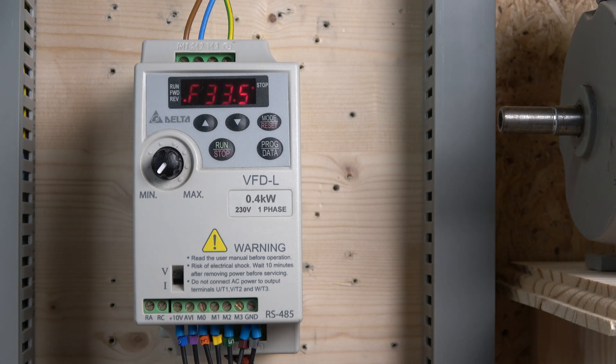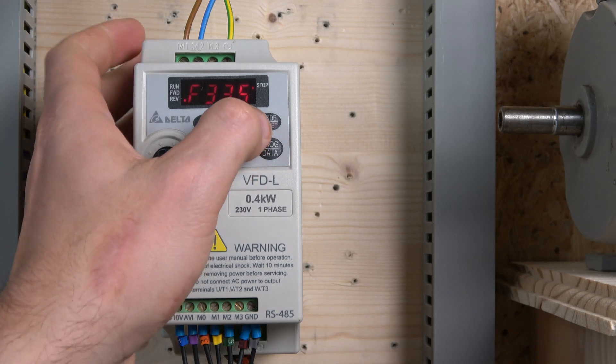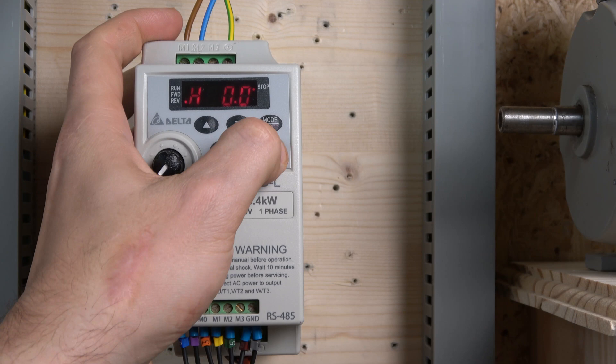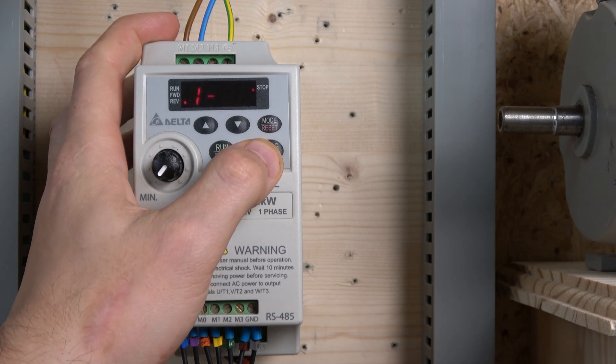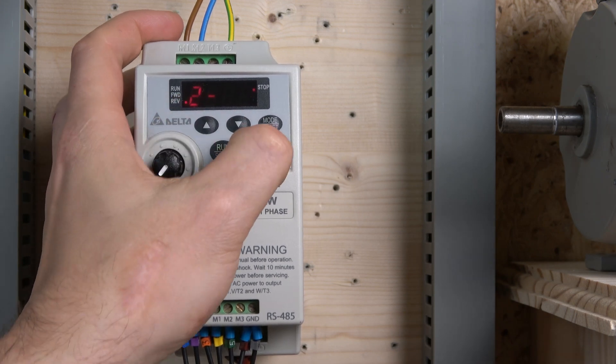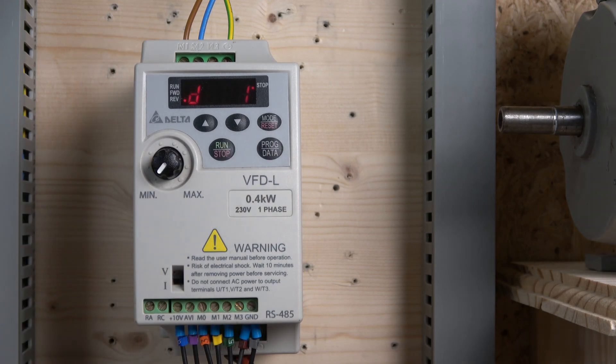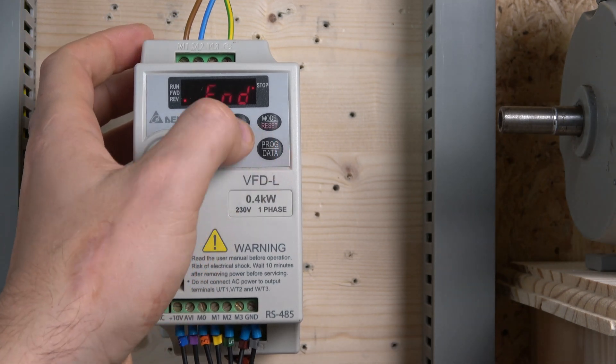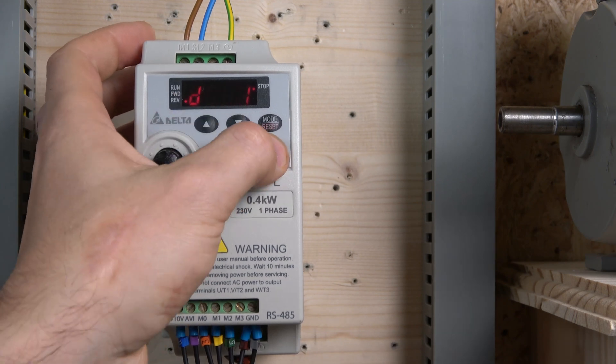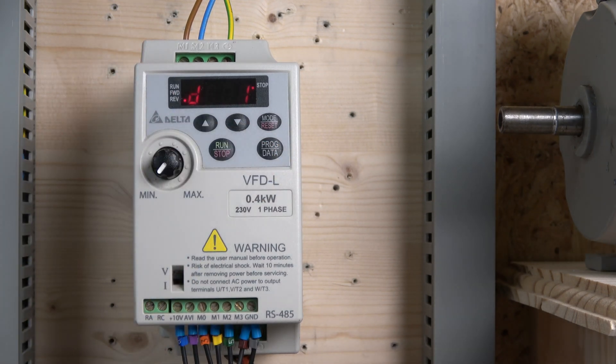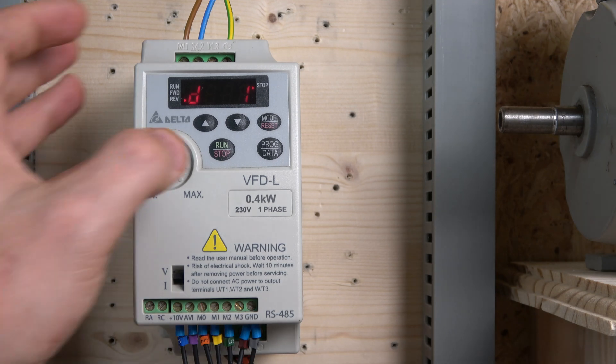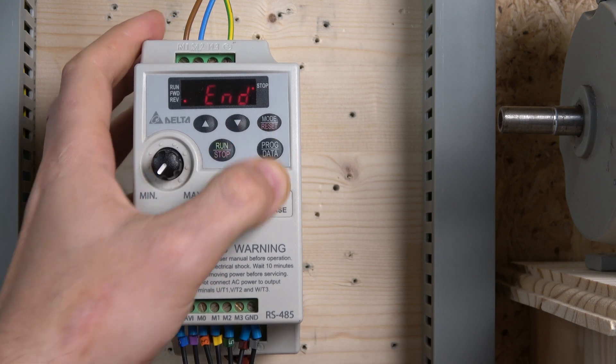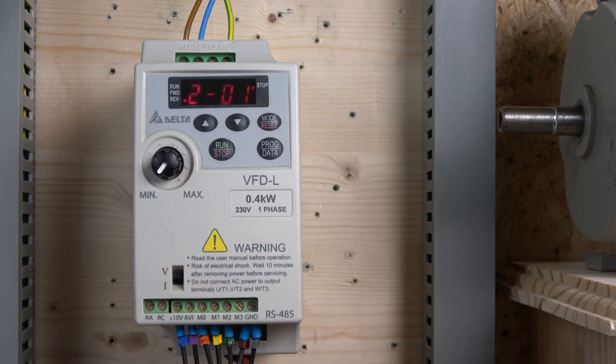For the parameters, the first parameter we're going to change is our source for the frequency command. That's going to be zero to ten volts which is set to one. And obviously the source for operation commands, that's going to be one as well for the terminals. So that's the first thing to do. Basically everything is going to be reading from the terminals.